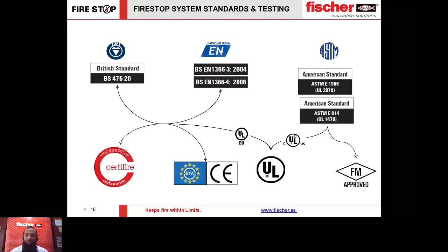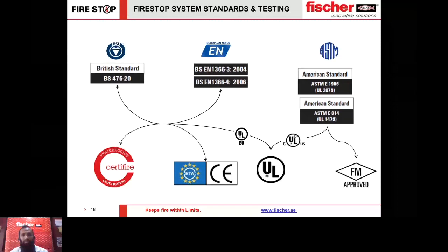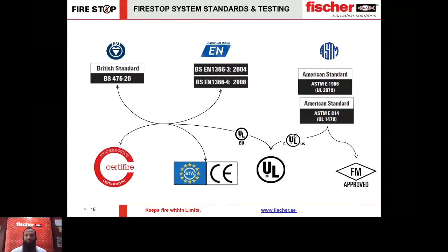If somebody asks me: give me a sealant which is two-hour fire rated — is that question correct? It is not a correct question, because the rating is always given to an entire system. We do have products tested in systems up to five hours rated, but if your fire rated barrier itself is just two hours, there is no benefit in giving you a five-hour tested product — it's just a waste of money. We want to ensure solutions are effective, efficient, and economic.